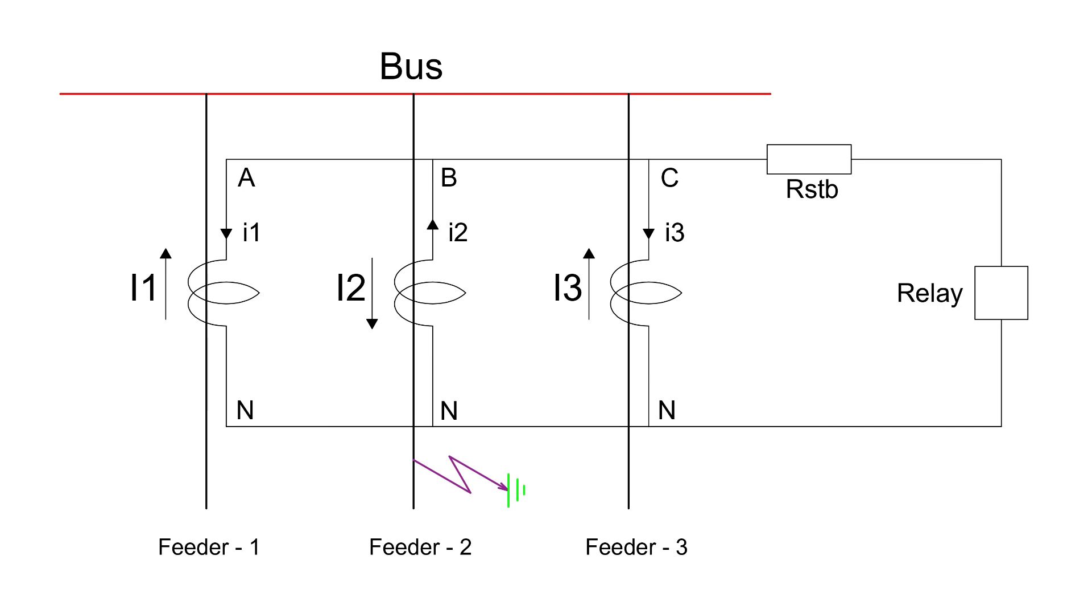The main cause of current flow through the relay coil in high impedance differential protection is the voltage across the terminals of the CT. Let's consider the worst case scenario where a CT gets completely saturated.